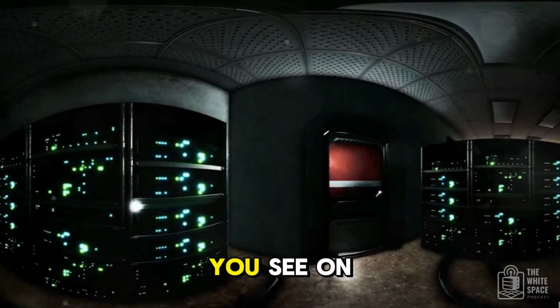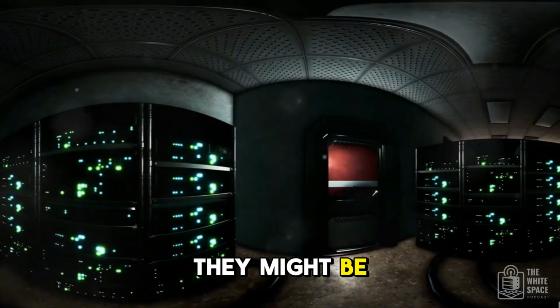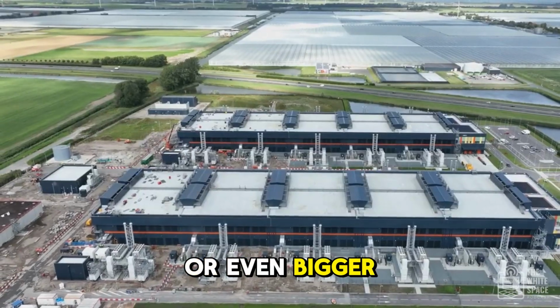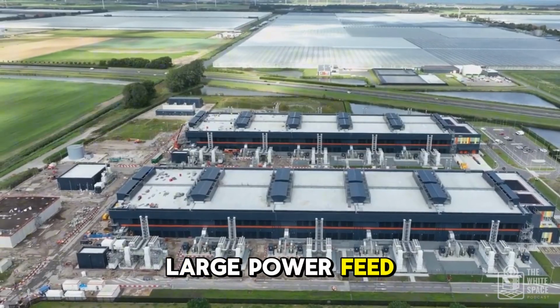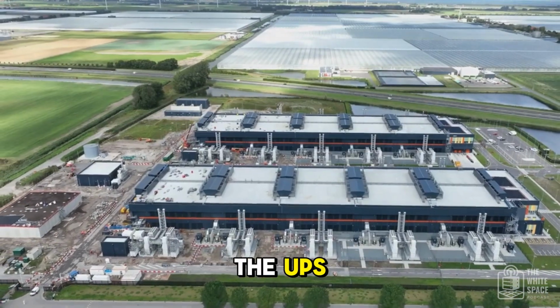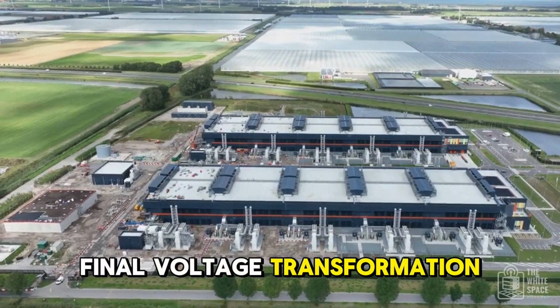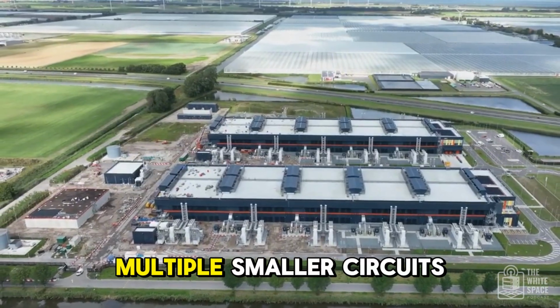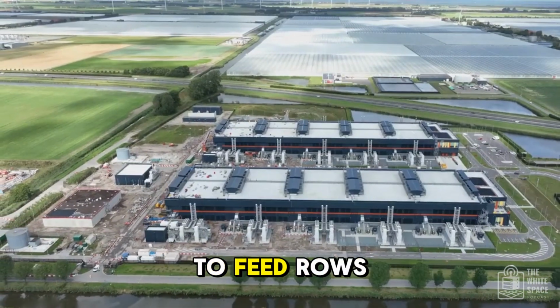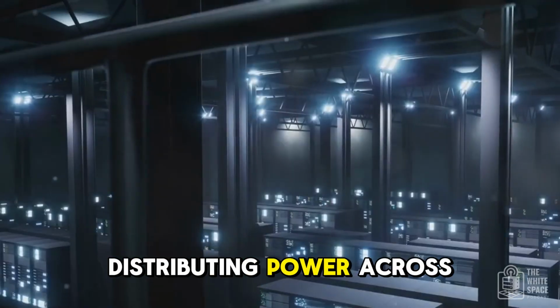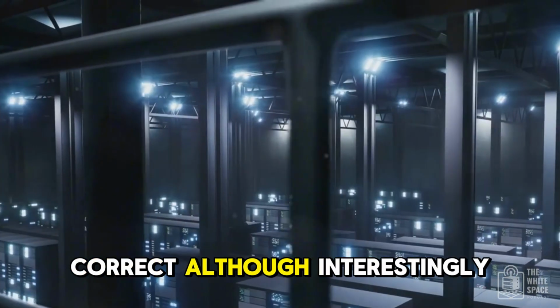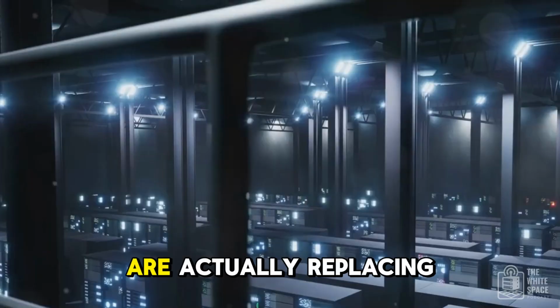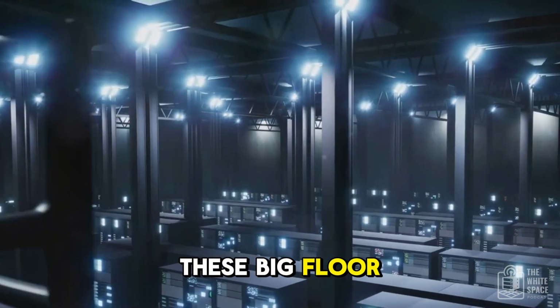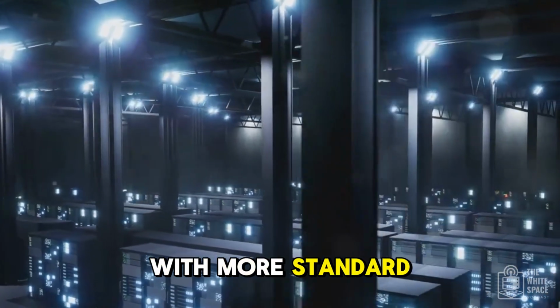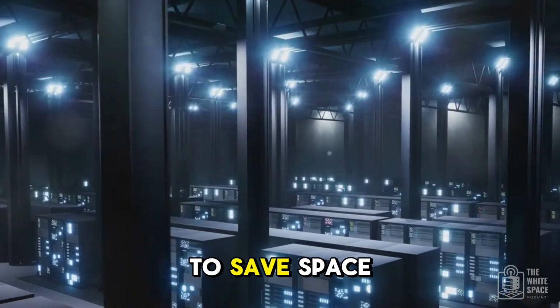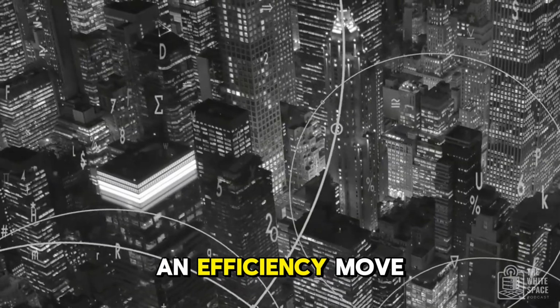Right, the big boxes you see on the data center floor. Exactly. They might be the size of a server rack or even bigger. They take a large power feed in, often directly from the UPS, maybe do some final voltage transformation, and then break it out into multiple smaller circuits to feed rows of racks. Distributing power across the room. Correct. Although, interestingly, some modern designs are actually replacing these big floor PDUs with more standard electrical distribution boards to save space and cost. It's an efficiency move.